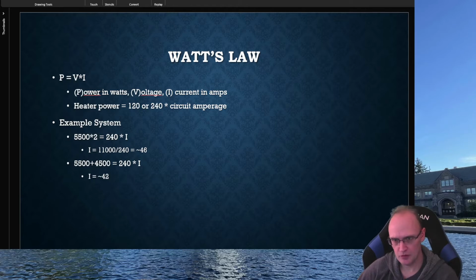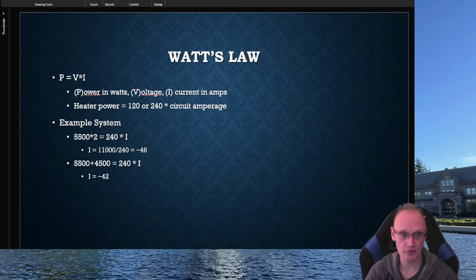Now, doing the math out on these, if we solve for the amps that these are going to end up consuming on the circuit, we have 11K divided by the voltage 240. That, rounding up, is about 46 amps. If we have a 50 amp circuit, that doesn't leave us with very much play for other components that we might have in the system. Have pumps, we're going to have sensors, we've had the microcontroller, etc.